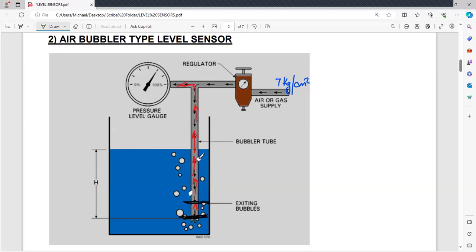If it gets a hole here, depending on how big that hole is, you will have air escaping over here instead of this back pressure. So that back pressure that is now going to act because of this particular hole in this thing, that back pressure is going to be less and less with more and more holes appearing. And therefore, the indication that is given over here, plus the indication given at the remote position, they are going to be wrong indications.